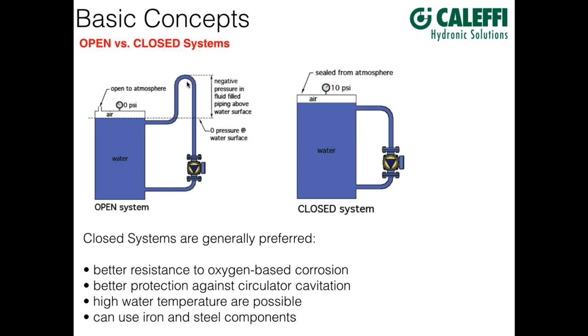The other issue with open systems is corrosion. Oxygen is always available to the water, and when that water cools, it's going to absorb gases from the atmosphere — oxygen and nitrogen. That oxygen gets carried around through the system, eventually corroding components like cast iron circulators, flow checks, steel expansion tanks, panel radiators — anything that is a ferrous metal. So we don't want to use those devices in combination with an open system. The majority of systems in North America are closed systems, sealed off from the atmosphere. The initial oxygen reacts with ferrous metal and is quickly locked up in an oxide without a constant resupply.